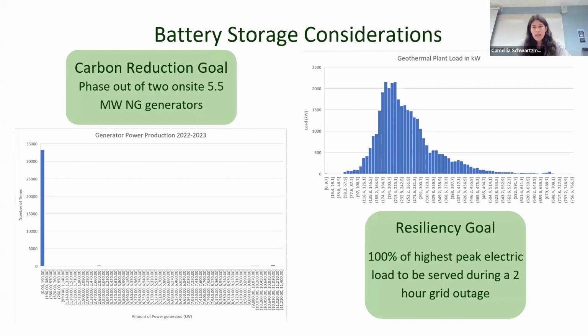use of those generators. And then the other goal, the resiliency goal, was to provide 100% of the highest peak electric load of the geothermal plant to be serviced through a 2-hour grid outage. We can also see the highest peak electric load is around 700 kilowatts, but the majority of the load is around 200 to 400. So we could propose a smaller battery, but we wanted to keep a larger battery system to provide the 2-hour full peak electric load outage.